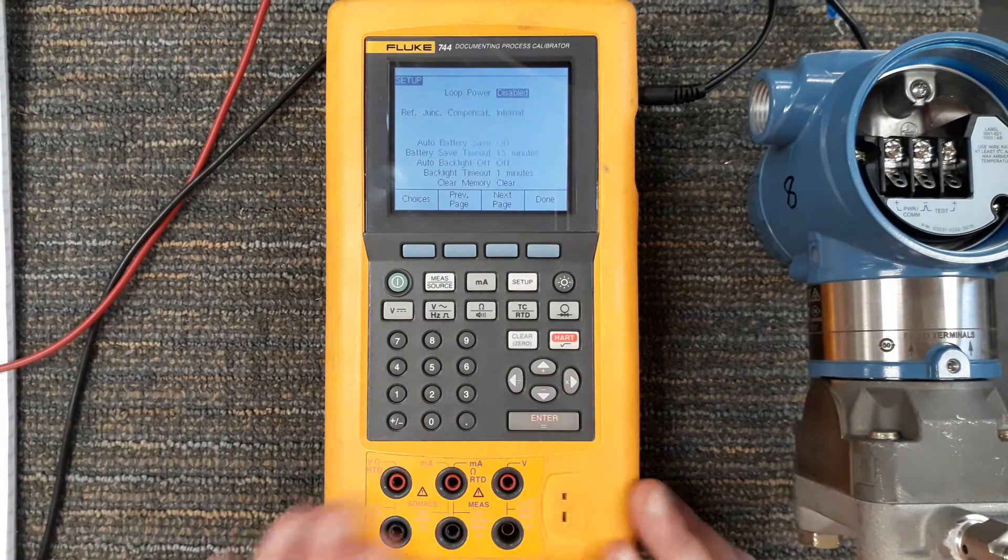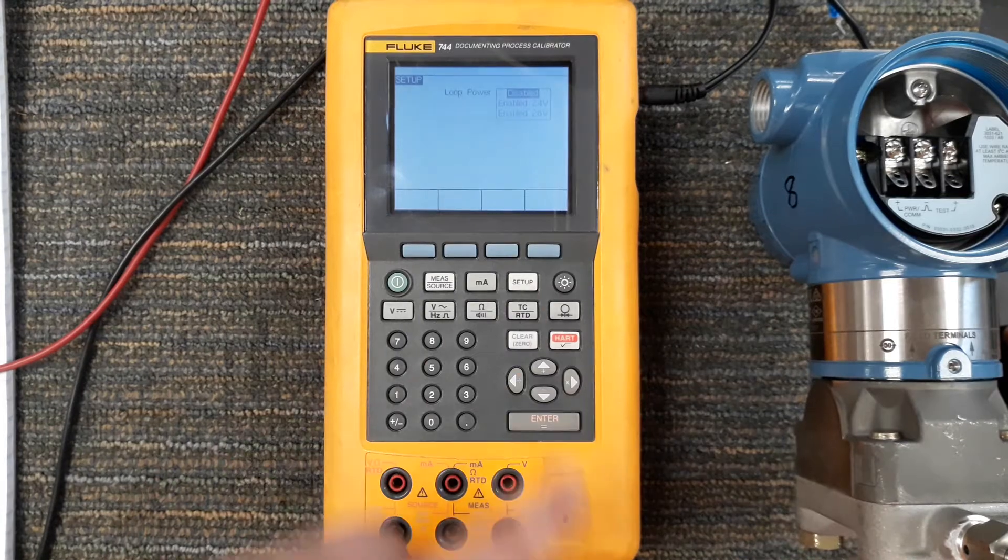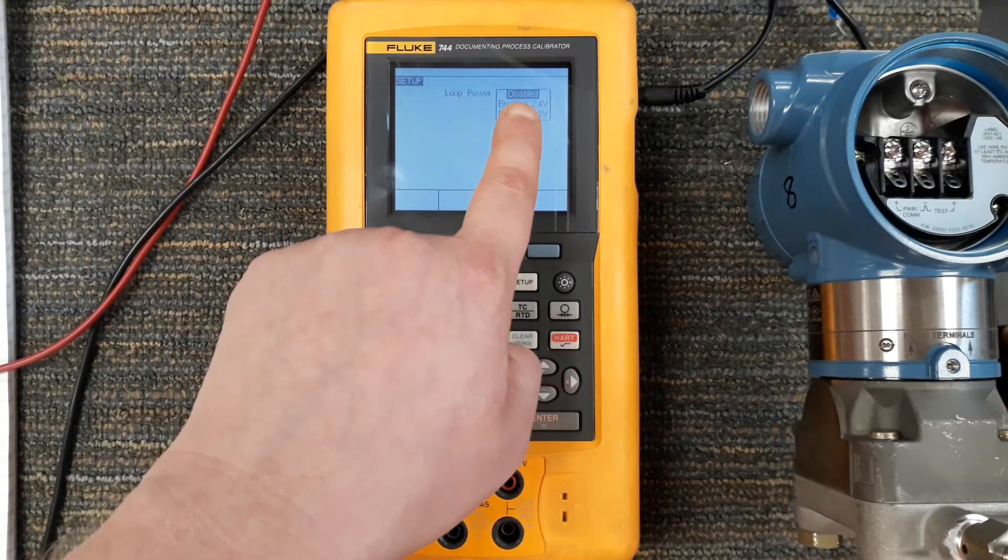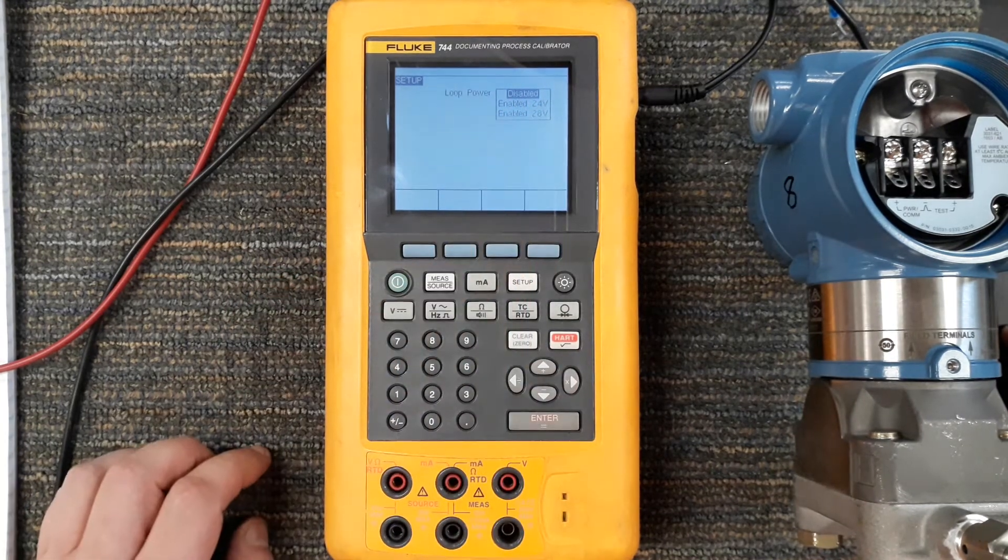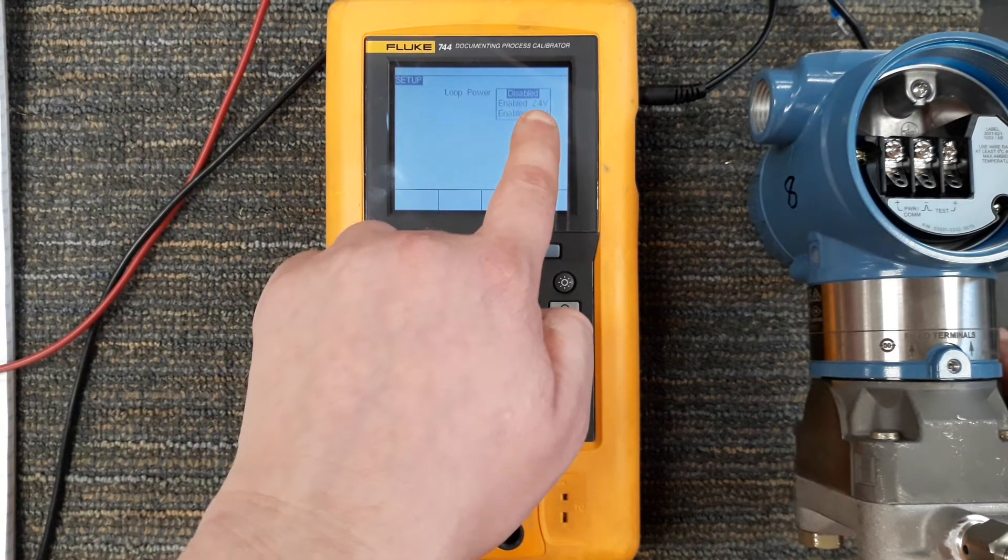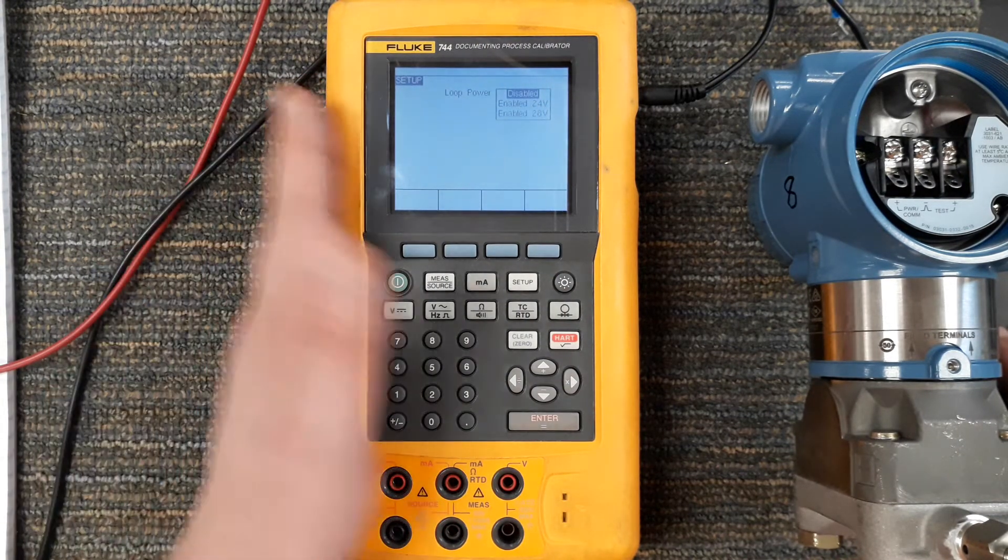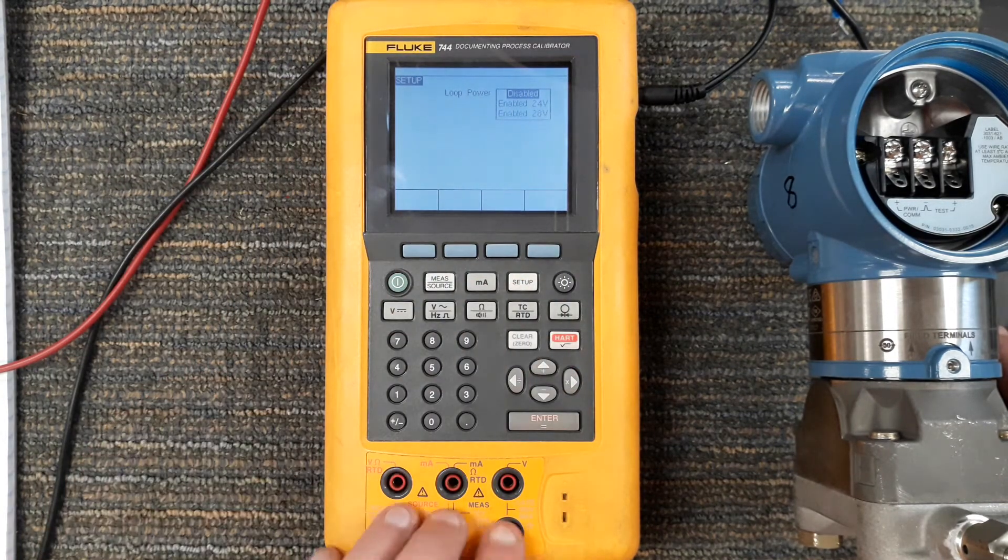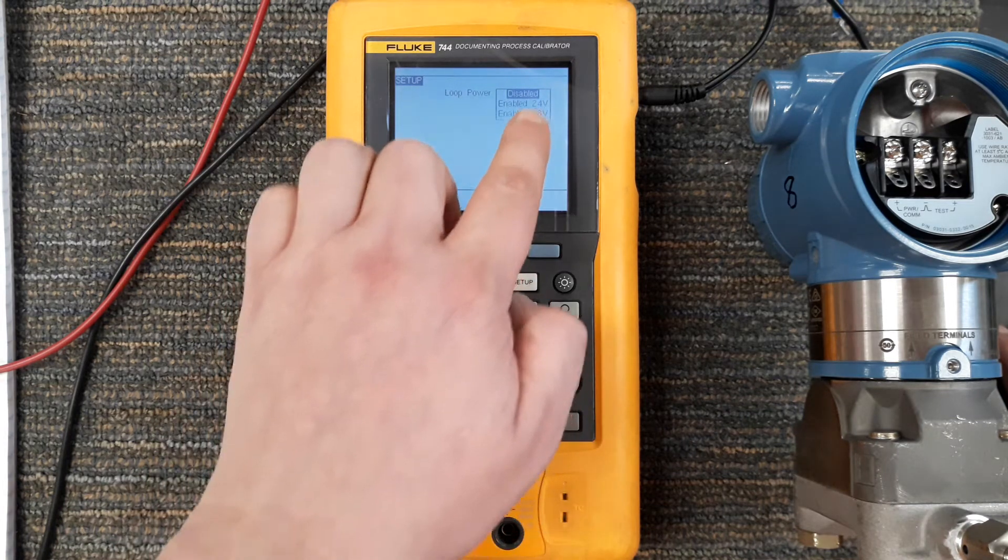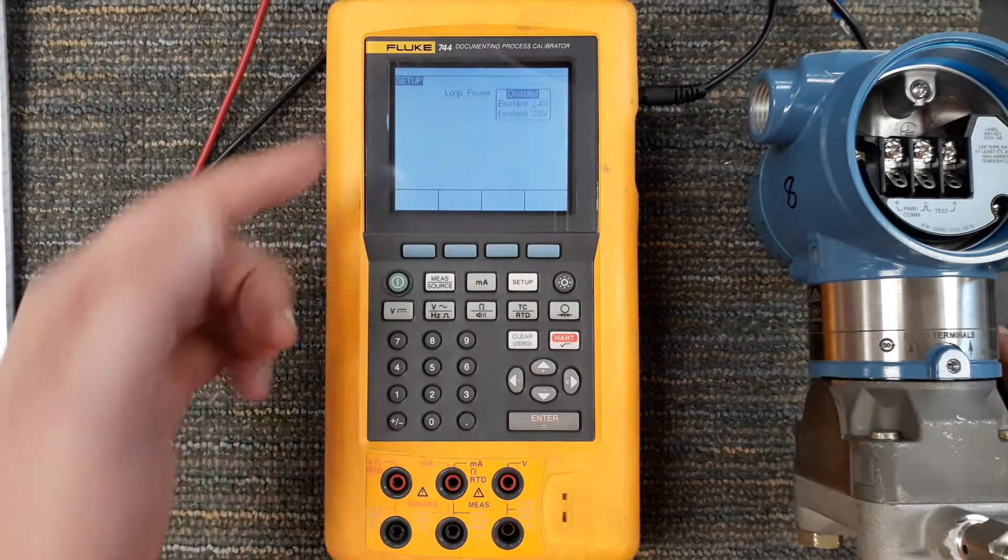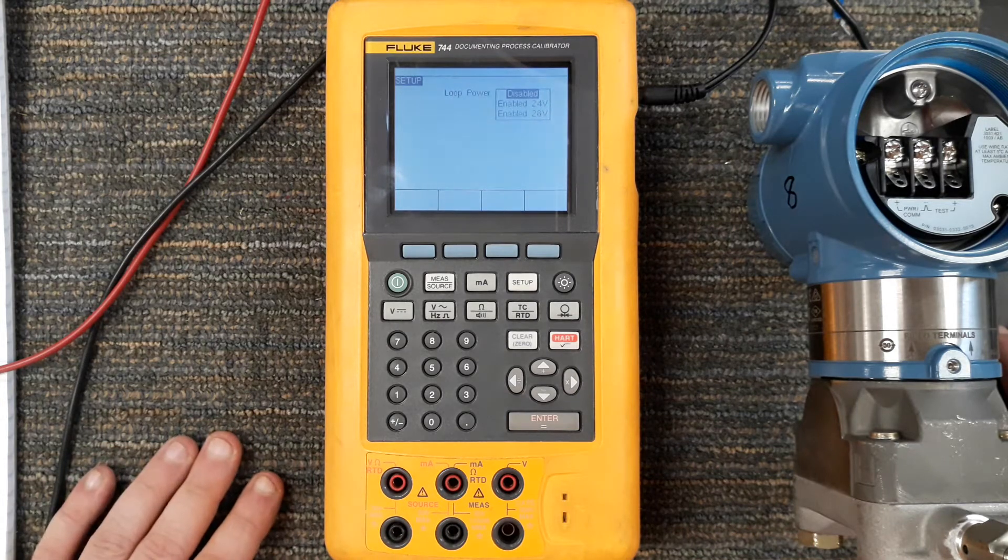Now I don't have any wires hooked up so I can go ahead and enable it just to show you. I'm going to hit enter on it because it's highlighted and then I have three options really: disabled, enable 24 volts, and enable 28 volts. This is the confusing part for some people because it leads you to believe that we're basically sourcing voltage which isn't exactly true. I mean we are, this thing is going to provide a fixed voltage of 24 or 28, but it confuses people when it comes to where they're going to hook up the wires. So if I were just to read this, enable 24 volts, oh I'm sourcing loop power, oh it's sourcing voltage, plug in here which is where the red V is but it won't work.